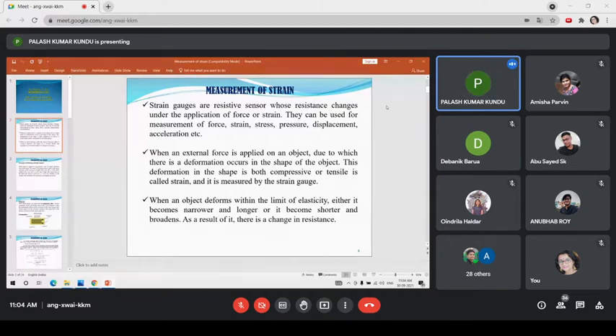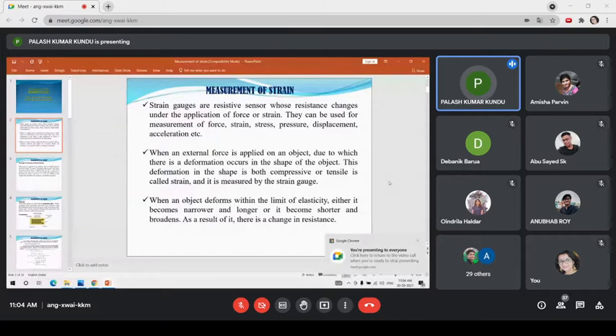How does it work? When an external force is applied on an object, deformation occurs in the shape of the object. This deformation is both compressive or tensile in nature - it is called the strain, and it is measured by the strain gauge. When the object deforms within the limit of elasticity, the ratio of stress by strain is constant, which is called Young's modulus. Either the object becomes narrower or longer, or shorter or broader, and as a result there is a change of resistance.